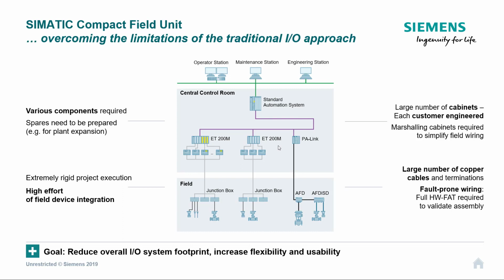Well, Profibus PA simplifies that for us a little bit. So it's one cable, again, our trunk out to our AFDs, but the PA DP link needs to sit in a cabinet. So we need 24 volts and a cabinet somewhere in a safe area. When we come down to the AFDs, we still have to follow our network design. So we've already highlighted the issues there.